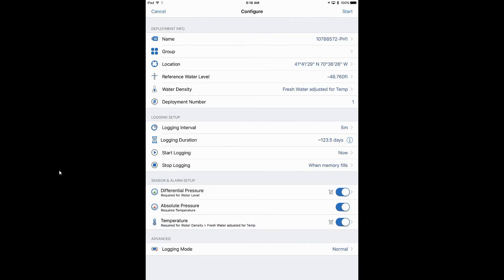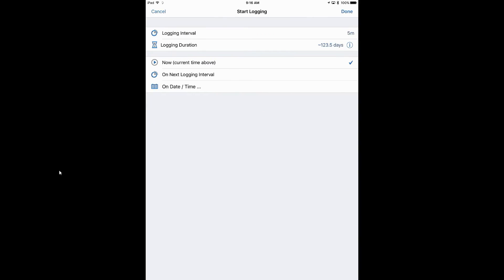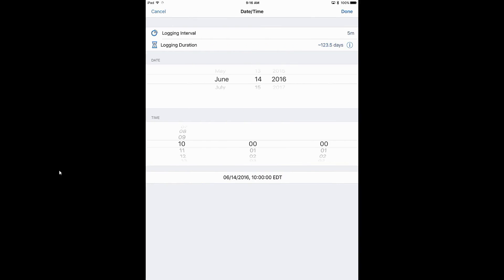We have basically 123.5 days worth of data before the logger takes its full memory action, which we'll talk about under Stop Logging. Under Start Logging, it asks how we want to start — we can start it now immediately, at the next logging interval (the next five-minute increment on your clock), or on a specific date and time, which is what we used to call a delayed start. This is a good feature if you have multiple loggers that you want to synchronize to the same start time.